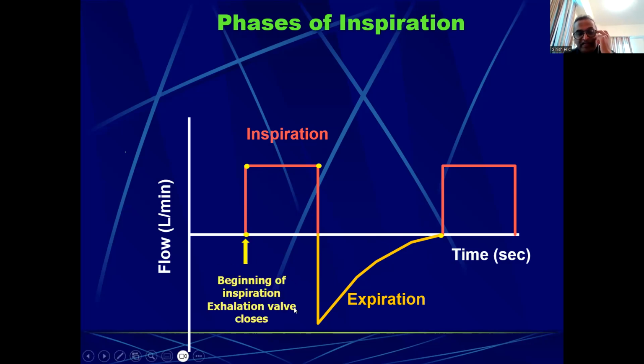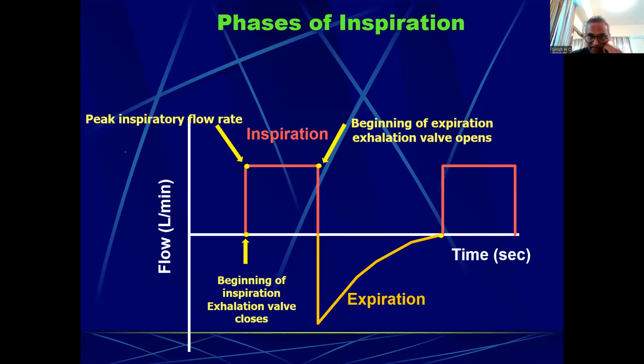So this is the beginning of inspiration, when the exhalation valve closes, and inspiration begins from the ventilator. Then a certain amount of flow is reached in order to achieve a certain volume in this case, or if it is a pressure ventilation, in order to reach a certain pressure. And then the exhalation valve opens. These are 3 important phases of inspiration, and every mode of ventilation depends on what happens during this. So if you understand these 3 phases, you will understand everything about ventilation.